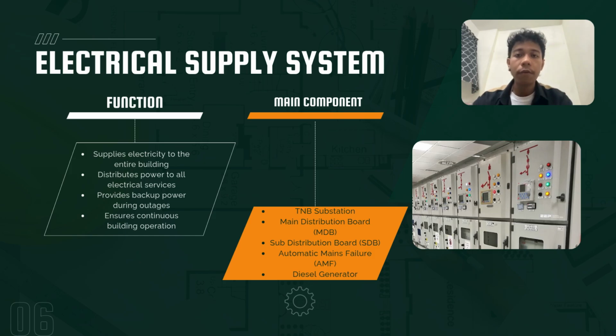The system consists of 5 main components. First is the TNB substation, which receives the main electricity supply from Tenaga Nasional Berhad. Next, the electricity passes through a transformer to reduce the voltage to a suitable level for the building. The electrical supply is then distributed through the main distribution board or MDB, followed by the sub-distribution board or SDB, before reaching the electrical loads throughout the building. To ensure continuous operation during a power outage, the building is equipped with an automatic mains failure (AMF) system and a diesel generator, which automatically provide backup power whenever the main supply fails.